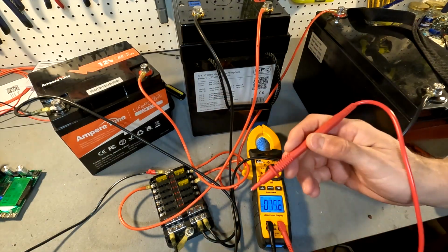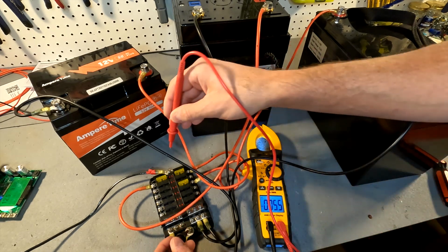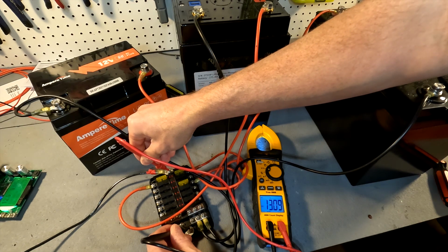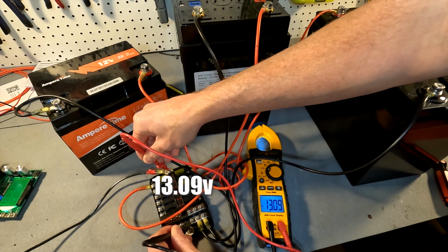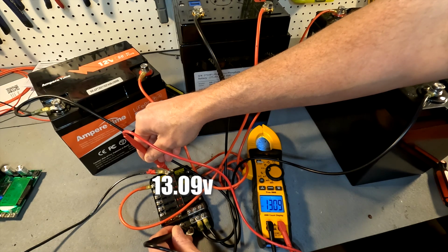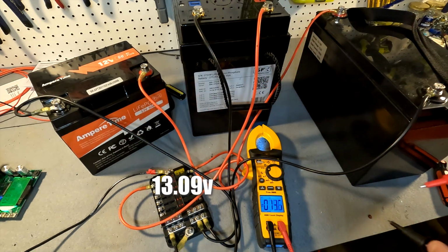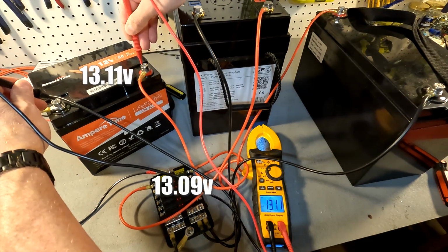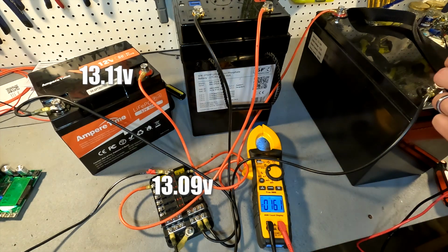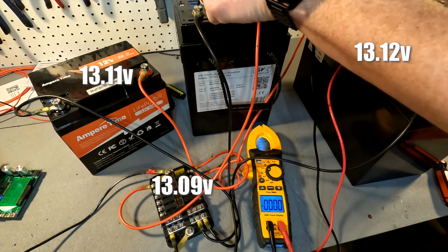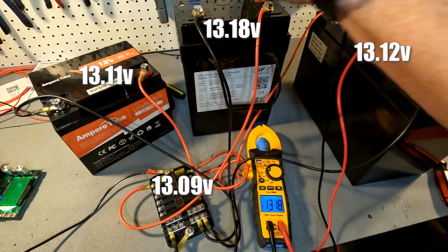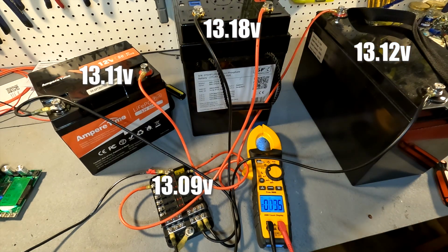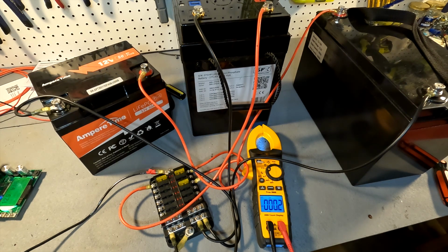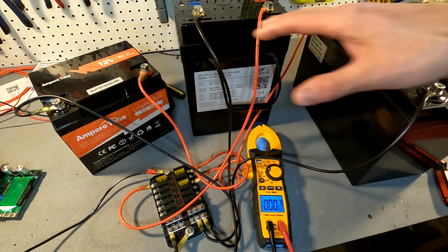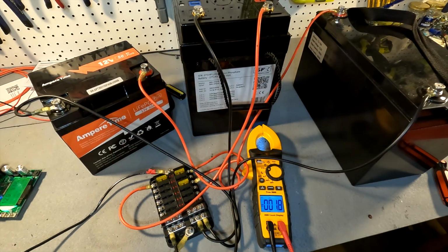Okay, first let's test the fuse block. It says 13.09. So this says 13.09, but the battery tester says 12.9. The 50 amp battery is at 13.11. The 100 amp battery is at 13.12. And the big 275 amp battery is at 13.18. Not bad when it comes to deviation of voltage, but I have a feeling as the test goes on, the voltage will get farther and farther apart. We'll just have to see.